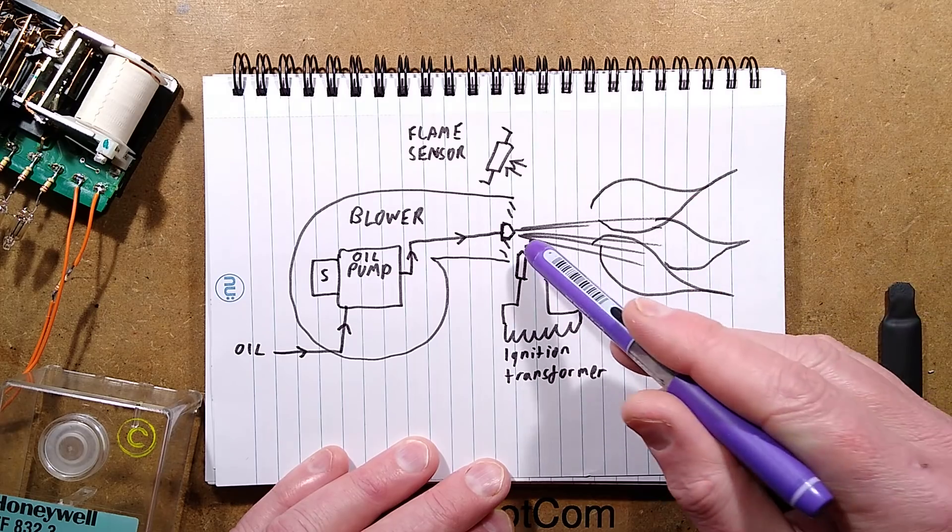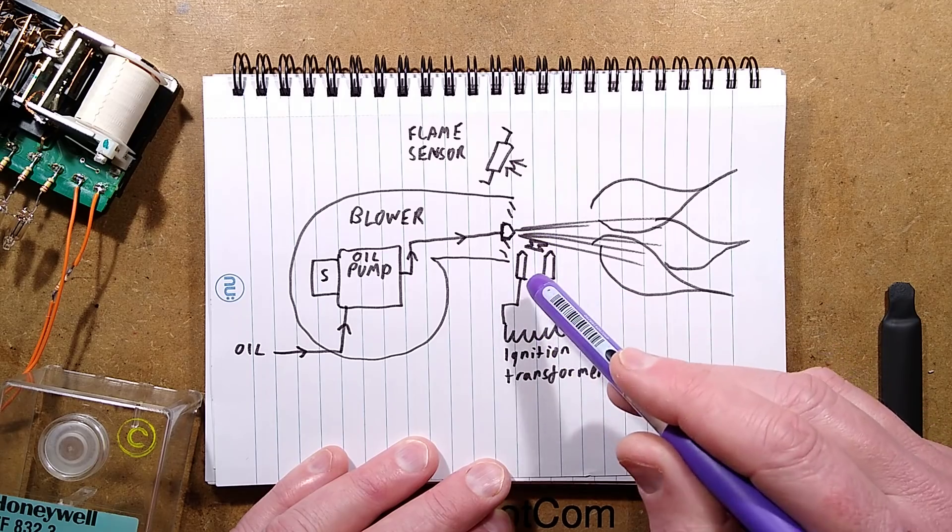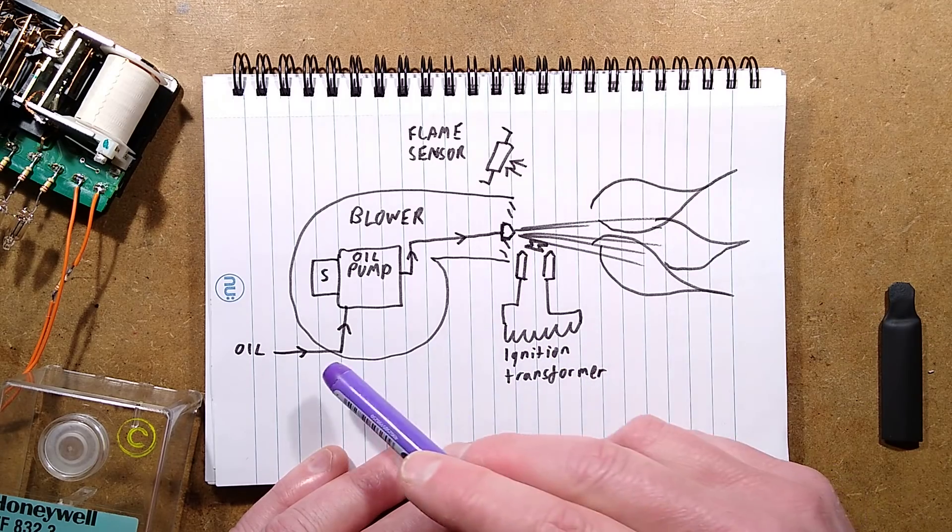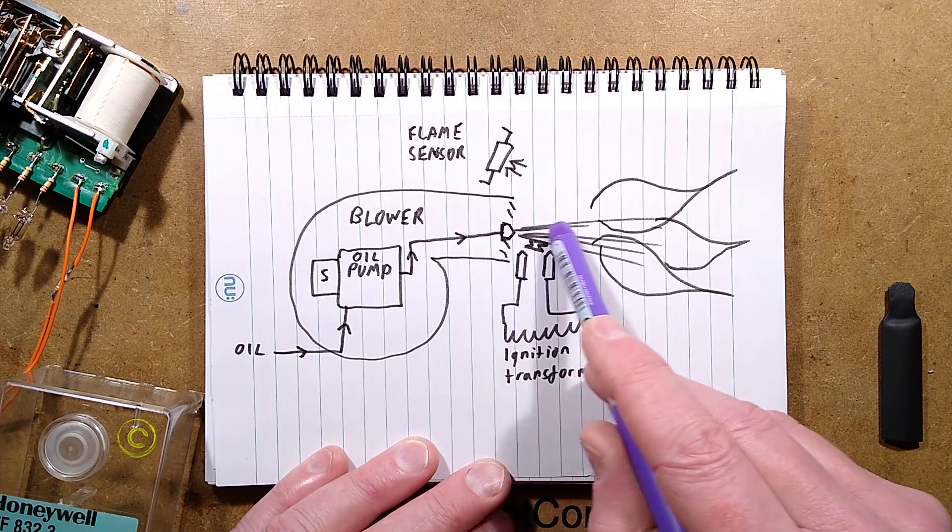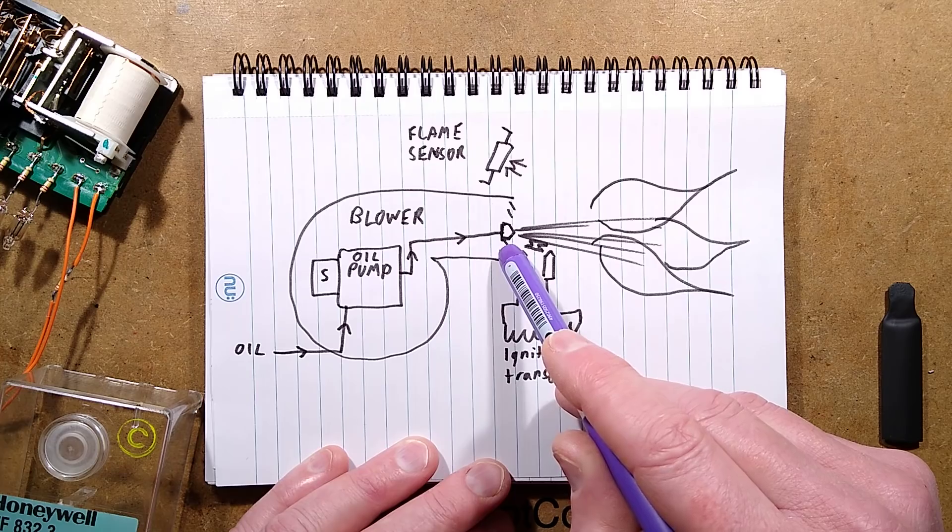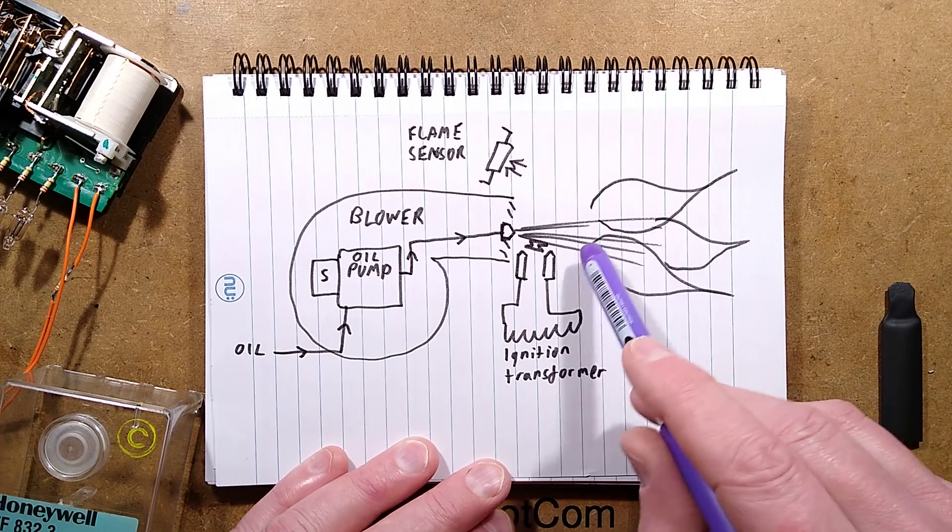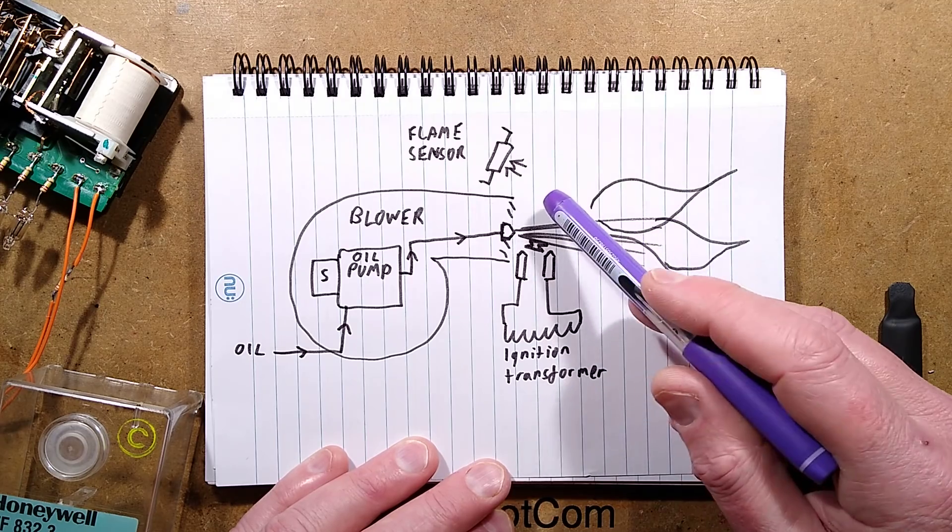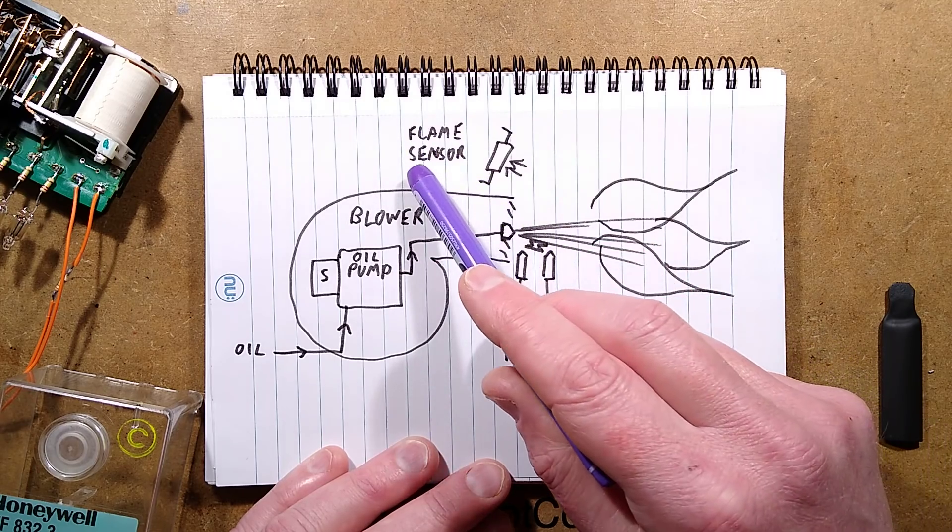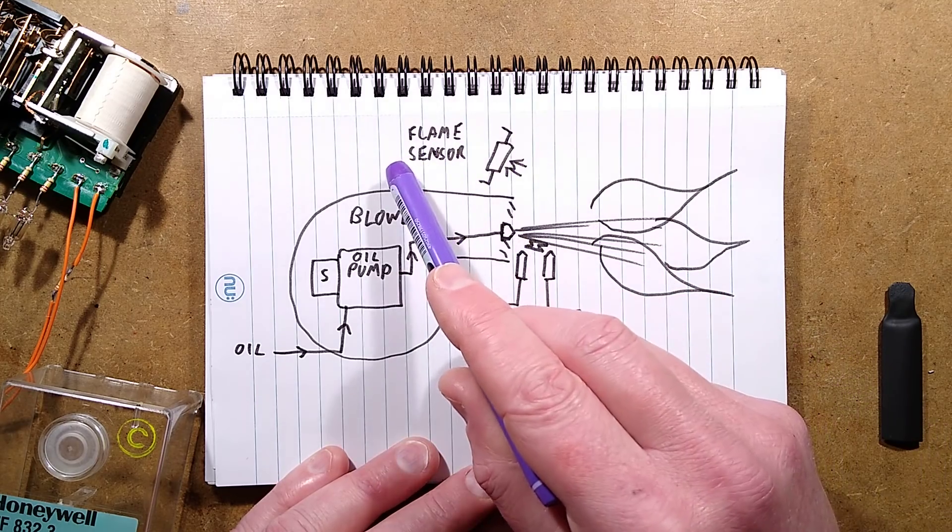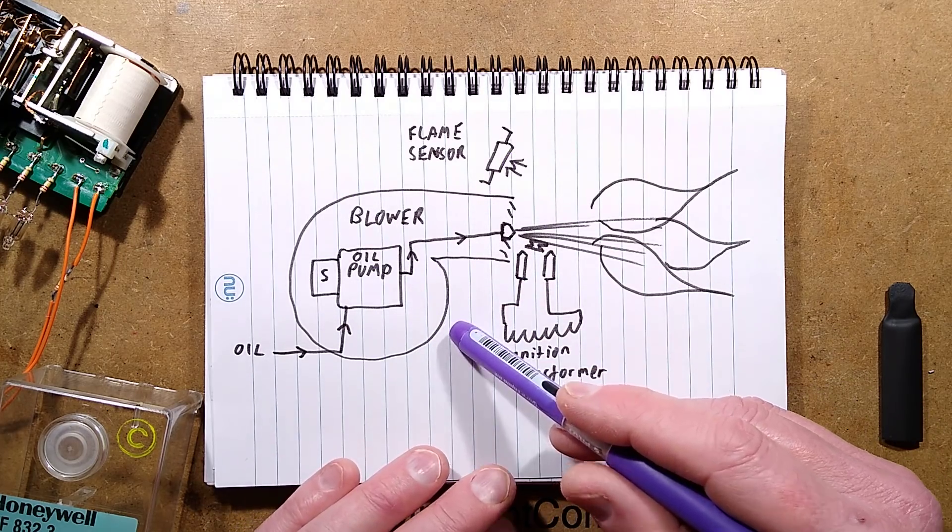The sequence of operation is that the blower starts up and the oil pump is just circulating inside, but it blows for a certain length of time to actually purge air through the system. At the same time, in this particular unit, the high voltage spark starts appearing at the nozzle. After it's purged air for a while, the solenoid operates and now oil will flow through the pump and it will be atomized from a fine jet that looks very similar to a 3D printer jet. If everything goes to plan, the spark ignites the oil vapor, it bursts into flames.